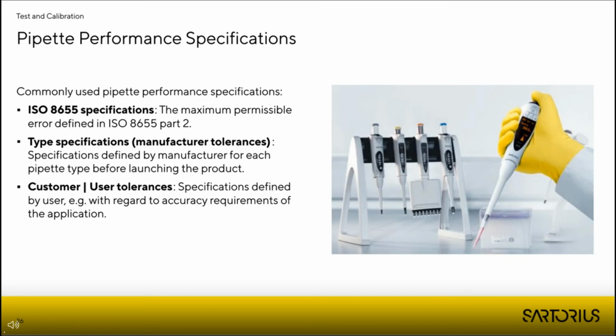As you know, during a calibration, the result can be compared against a performance specification. Three different performance specifications are common here. First, the ISO specs that are in the respective part of ISO 8655, for example, the specifications for a pipette in part 2. The second performance specification is the manufacturer specification. These manufacturer specifications are usually much smaller than the ISO specs.